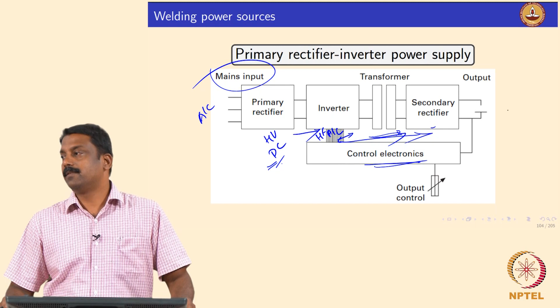It's clear? The circuit looks very simple. So you will have a primary rectifier from the 3-phase mains, you will have a single phase high voltage DC, and that is sent to an inverter. The inverter converts high voltage DC into high frequency AC, and this can be transferred to our welding circuit, right, using a simple transformer, because it is already high frequency high current AC. So you just need a very simple transformer to transfer the current, and then you may have a rectifier to convert this AC into DC again, and you will have an inductor circuit and then electronic regulation to control the output.